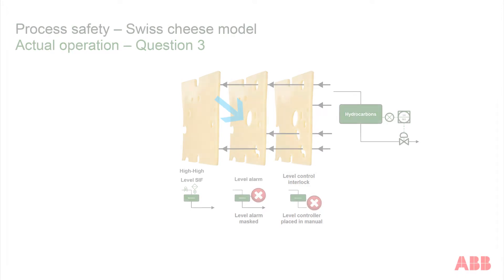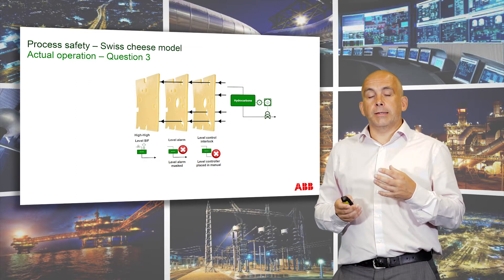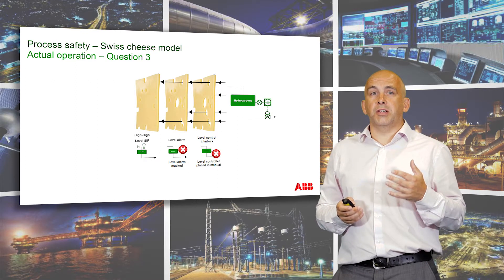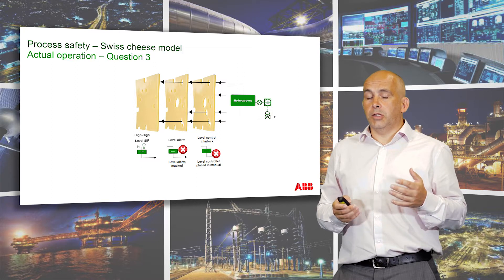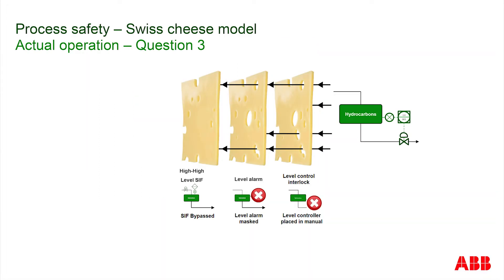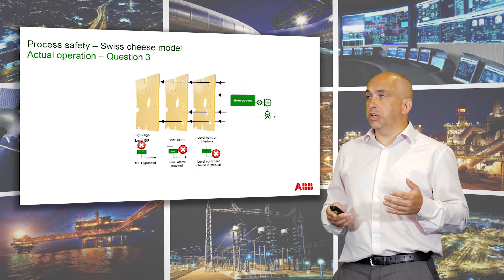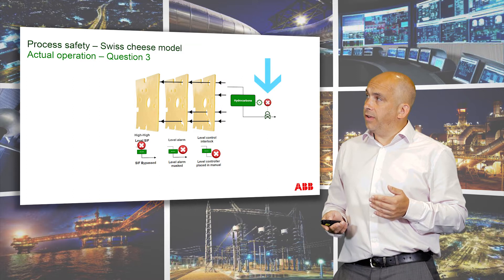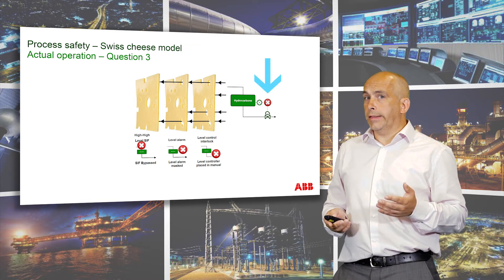Some time later, a maintenance person comes along to do a proof test on that final barrier. To do that task, they have to bypass or override that particular safety instrumented function. As soon as that override is placed, the third barrier becomes ineffective and we introduce another hole in that final slice of Swiss cheese. Now we've got nice hole alignment in our Swiss cheese model, such that when we have a failure of the level control, we get the incident.